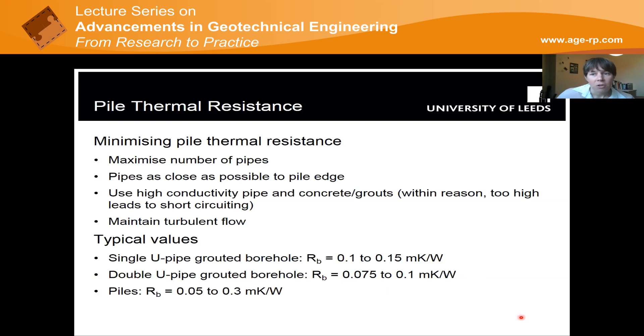Comparing that to typical values for traditional borehole ground heat exchangers, you'll see the lower range for piles is more efficient than a typical borehole, but the upper range is less efficient. This is because you have so many more options about geometry, since you have a bigger pile in which you can choose how many pipes and where to put them. I'll show you the impact of some of those things.